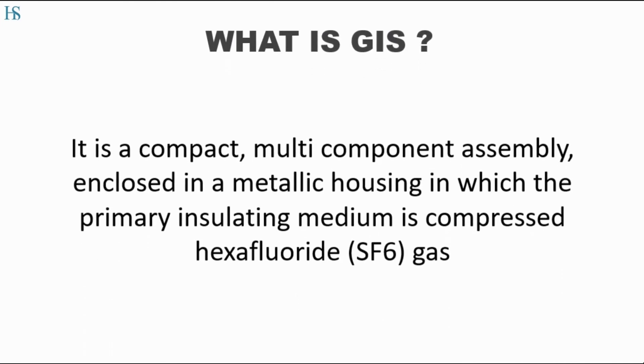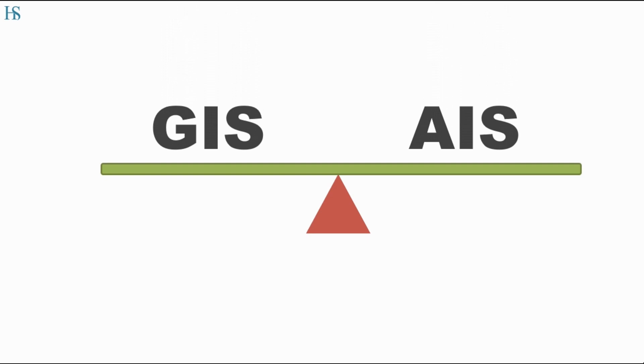So what is GIS? It is a compact multi-component assembly enclosed in a metallic housing in which the primary insulating medium is compressed sulfur hexafluoride, i.e. SF6 gas. This SF6 gas acts as an insulator between the live parts and the earth metal enclosure. GIS contains the same compartments and components that we see in a normal AIS, i.e. air insulated substation, but the only difference is in the insulating medium.